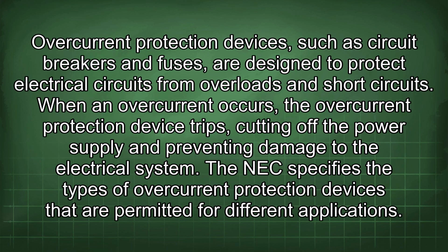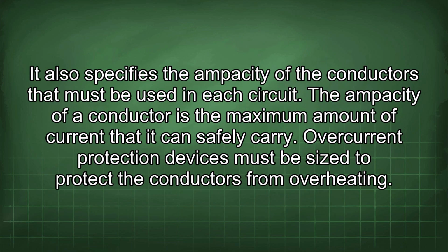Overcurrent protection devices, such as circuit breakers and fuses, are designed to protect electrical circuits from overloads and short circuits. When an overcurrent occurs, the device trips, cutting off the power supply and preventing damage to the electrical system. The NEC specifies the types of overcurrent protection devices that are permitted for different applications. It also specifies the ampacity of the conductors that must be used in each circuit.